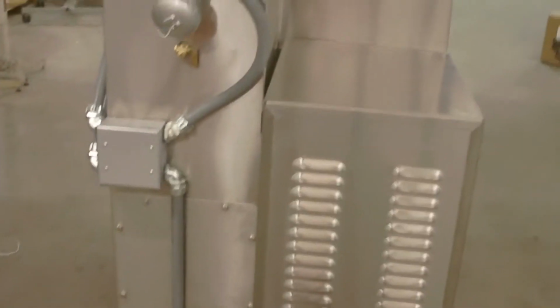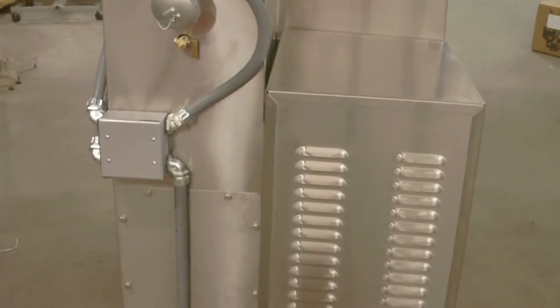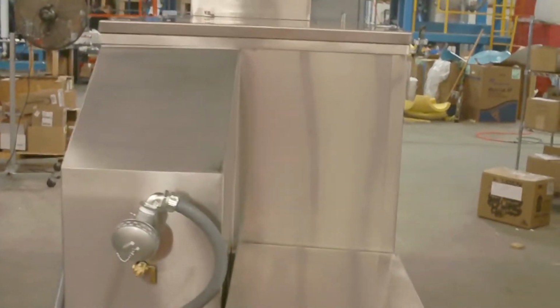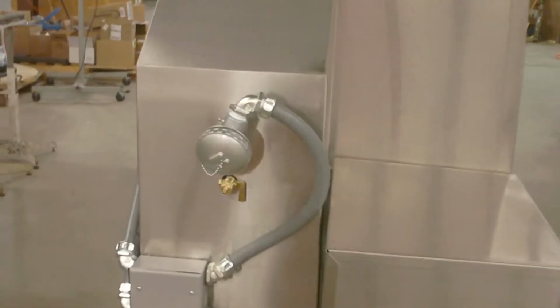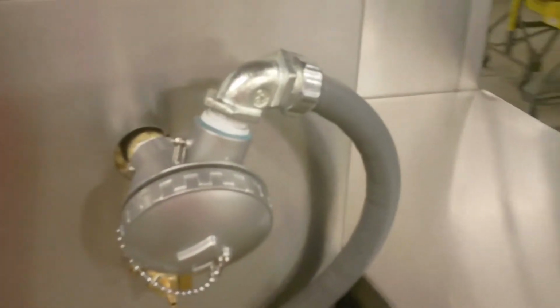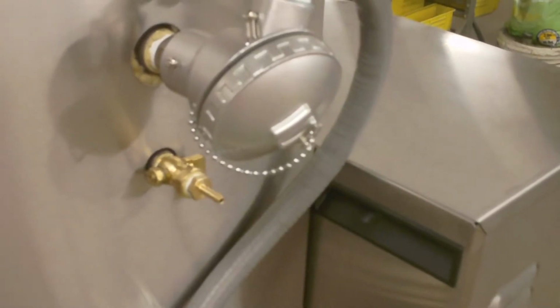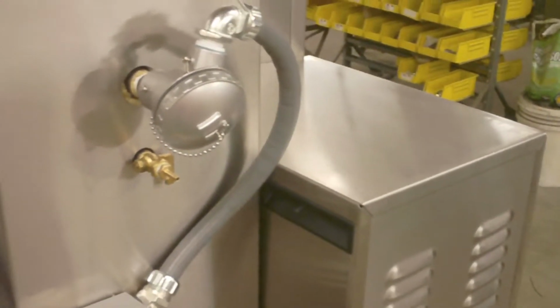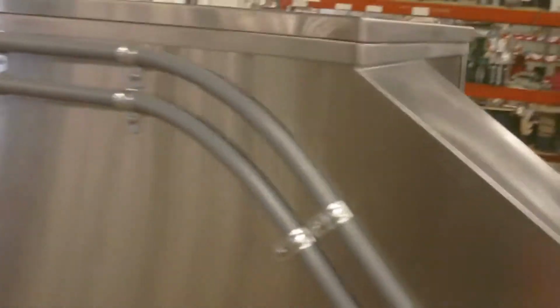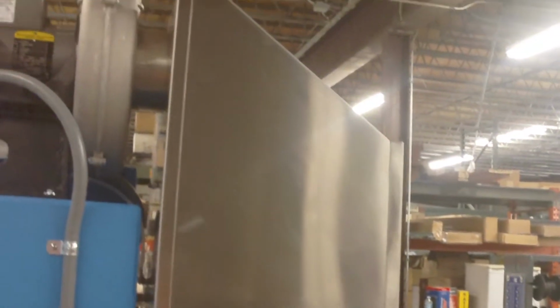In the back we have our burner, which is not covered by a shroud right now, and this is the chimney. When the hot air comes through out of the heat exchanger, it goes up and over the surface of the boiling liquid. Right there you can see we have an air temperature thermocouple, and also right below it there's a connection where you can get a combustion analyzer and check your combustion levels. There you have your aux panel for the unit. When the air blows across the surface of the water, it gets pulled up through there, which goes through the mist pad, and then out, and then through a pipe through the ceiling.